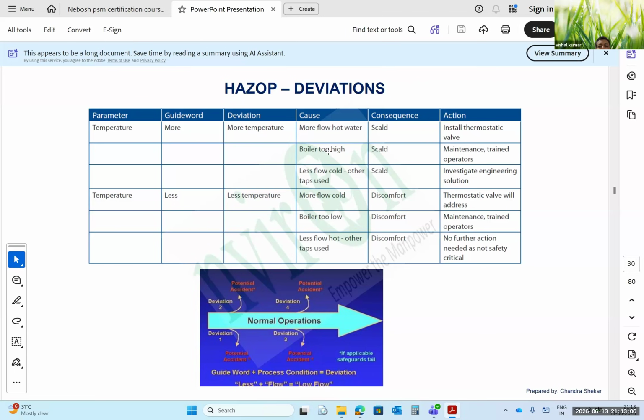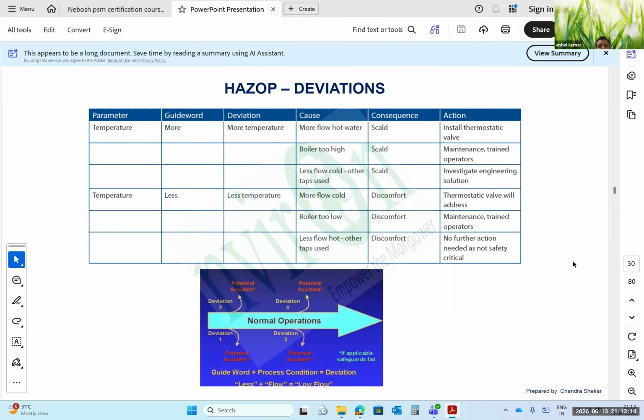Third deviation - what was the cause? Maybe for high temperature, there is less flow of cold water - the quantity is not enough to cool the system. What is the consequence? Scald can form. What action can we take? We investigate an engineering solution and can have extra supply of cold water to the system.